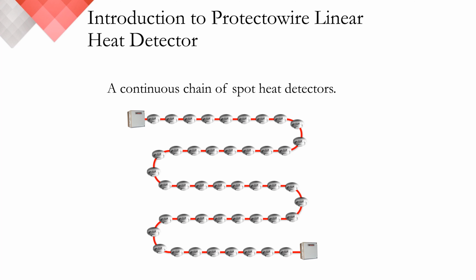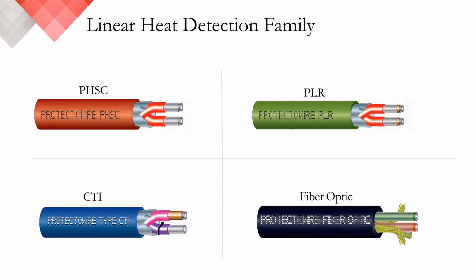Linear heat detection can be best described as a continuous chain of spot heat detectors, with the ability to sense heat or sudden increase in temperature anywhere along its length. A common misconception is linear heat detection comes only in one form. I'd like to take a quick moment to introduce the family of linear heat detection that has been developed over the years to meet a variety of challenges. To start, there is the PHSC series detector, which stands for Protectowire Heat Sensitive Cable. This is the product most widely used and the detector that most relate to when they hear the name. Comprised of two steel conductors, the PHSC series can be integrated into any conventional or addressable system. However, there are limitations when considering equipment, which we'll get into in a few moments.